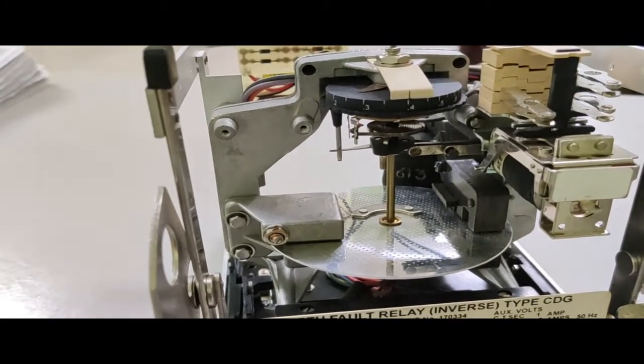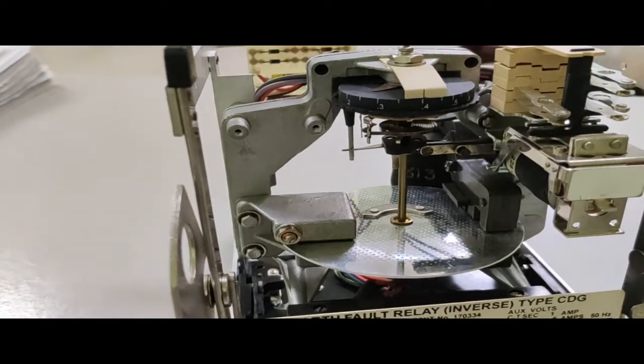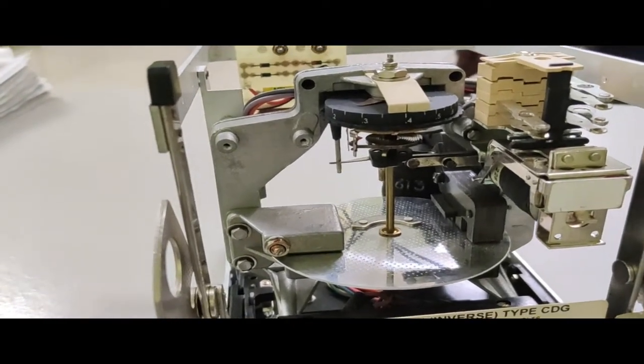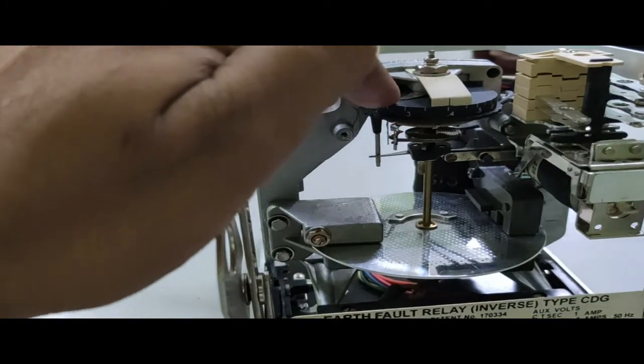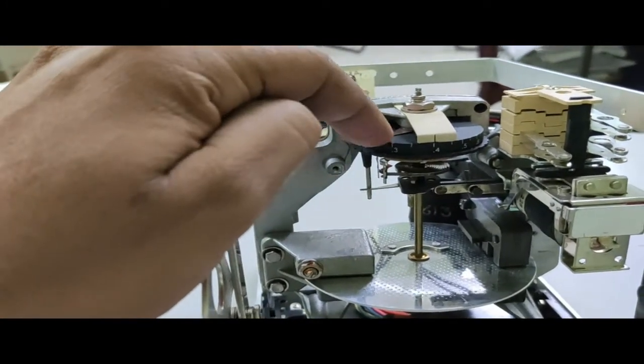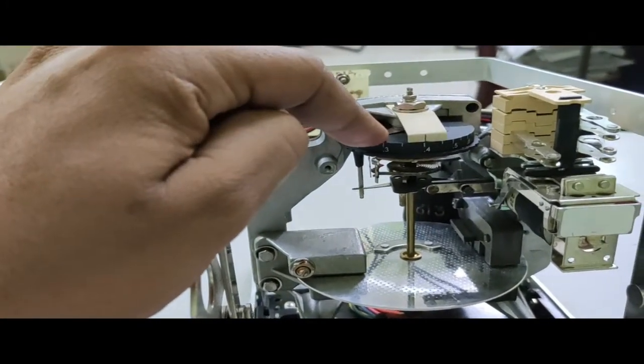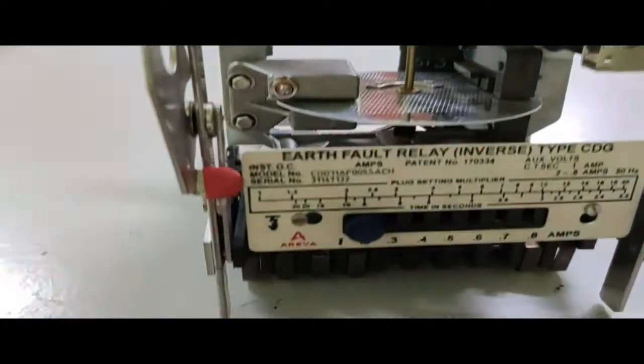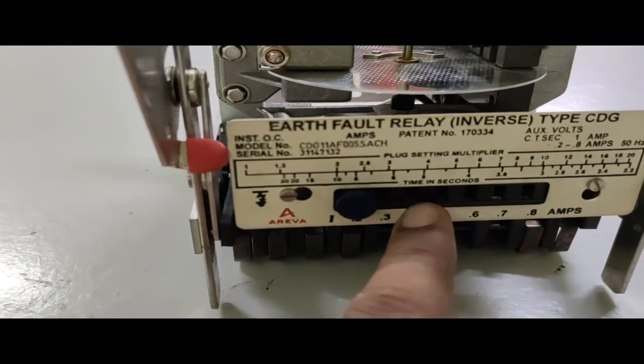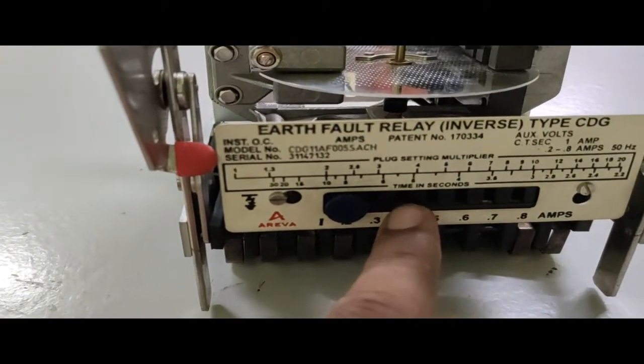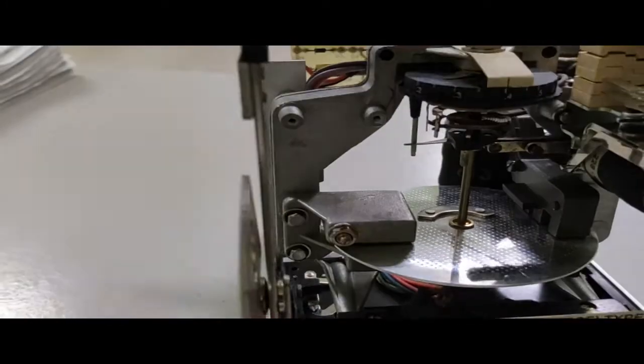So within this time if the fault is cleared, then the relay will not generate the trip signal. This is called the time setting multiplier. Using the time setting multiplier we can adjust the relay operating time, and using the plug setting we can adjust the relay operating current. Now how does this work?